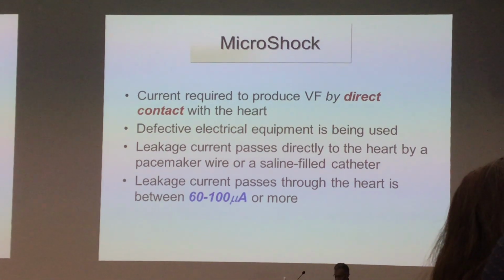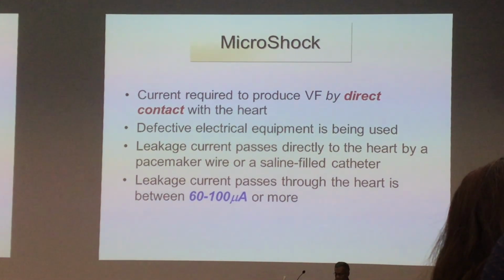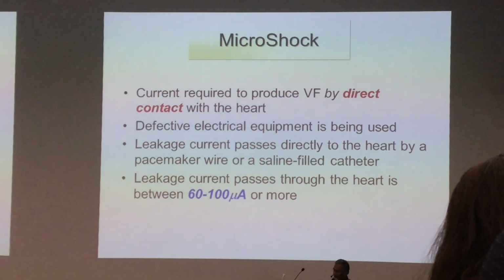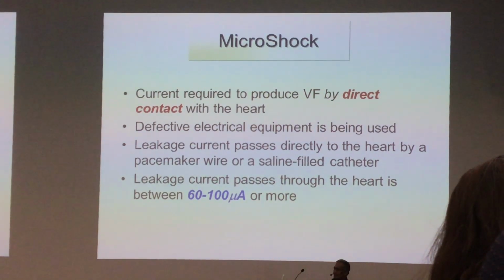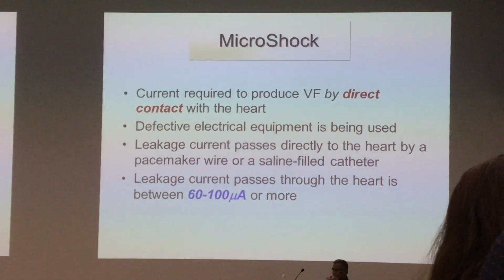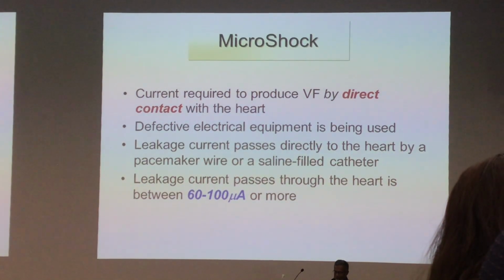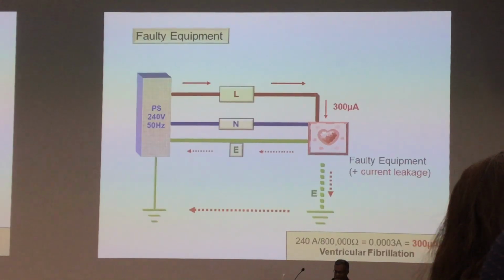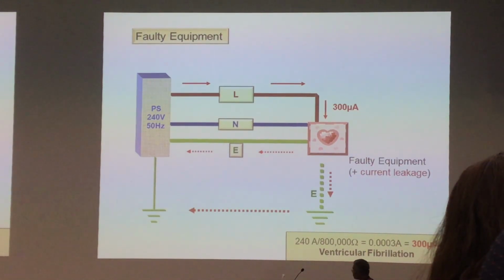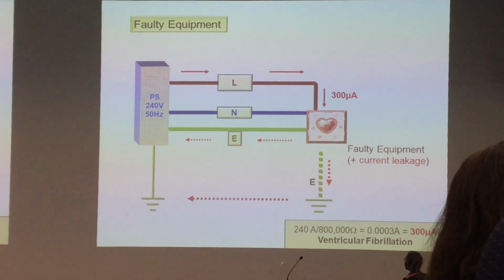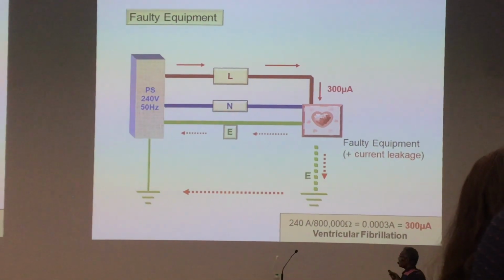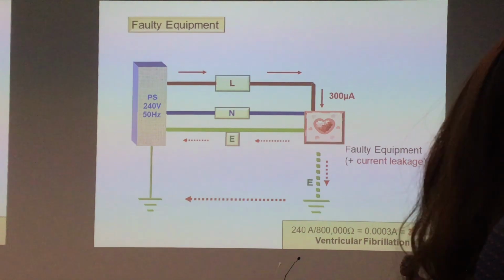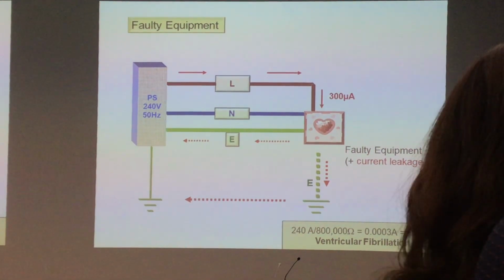But in our normal practice, we seldom see this because we assume the machine is okay, most times okay. We never know. Once in a while, because of an unfortunate day, very unlucky, we end up with this unexpected detrimental event. For example, the machine is faulty, the current leak is very little, say 100 microamp, but you are handling the heart. You are putting a CVP into the heart. So a small current, for example 100 microamp, passing through the heart ends up with VF.